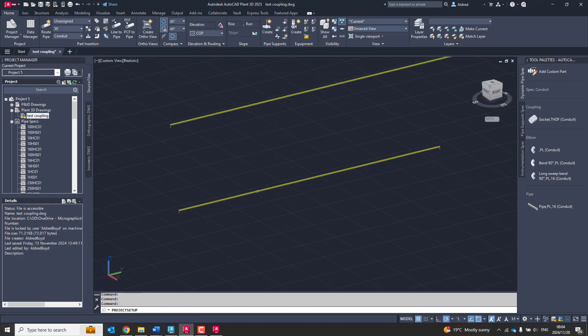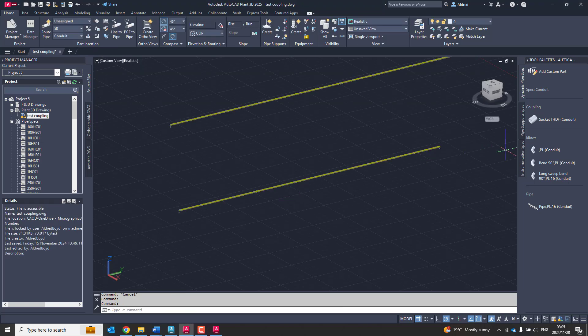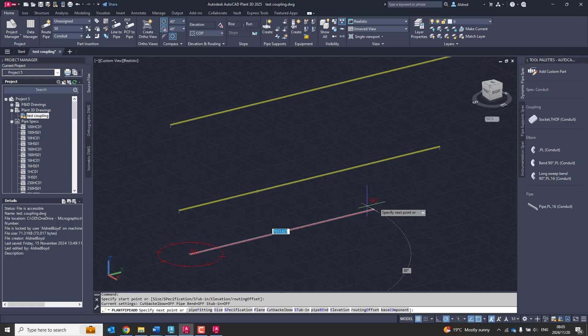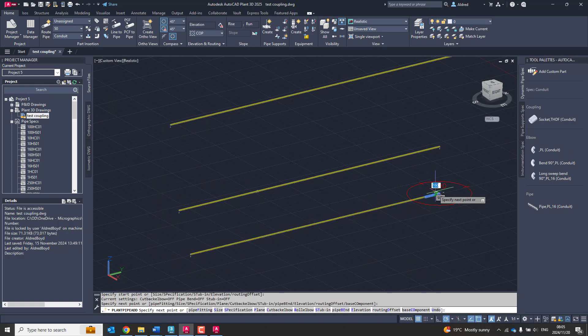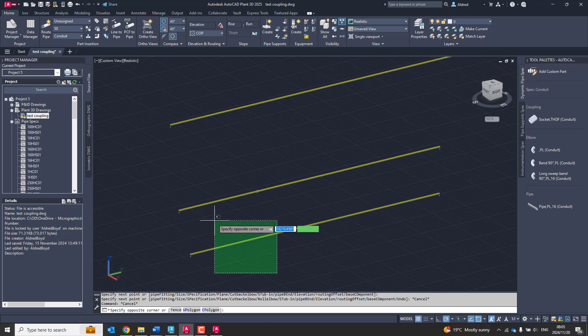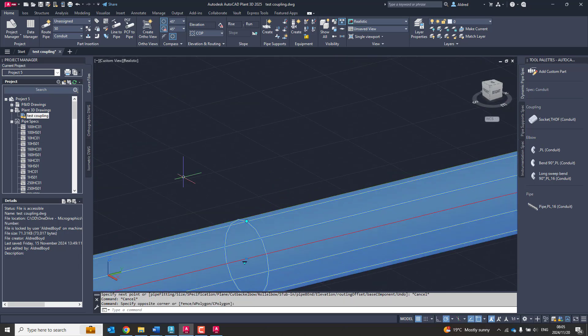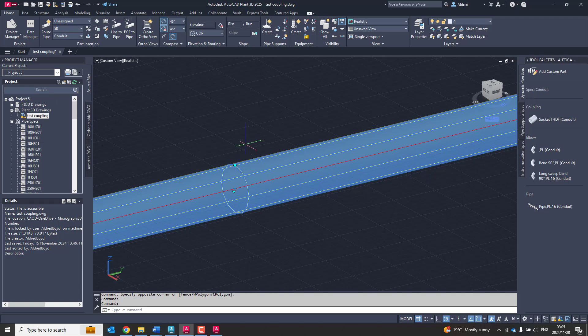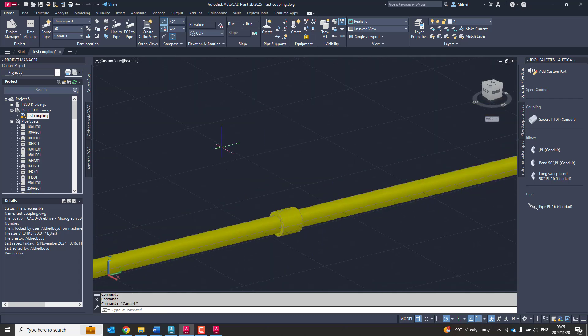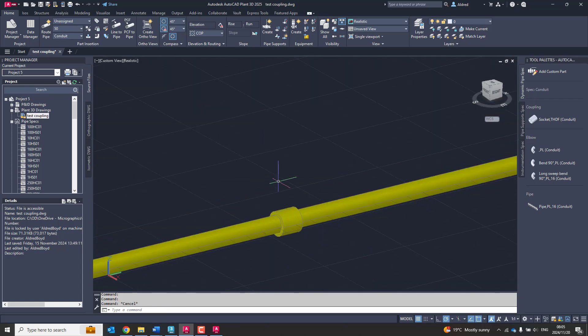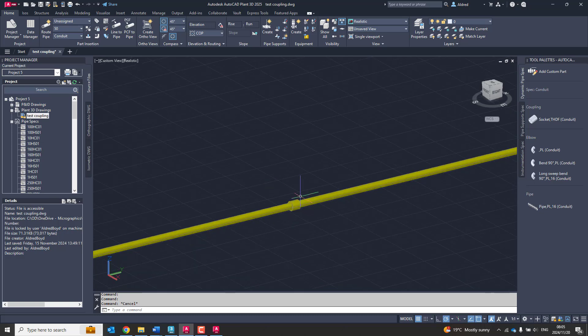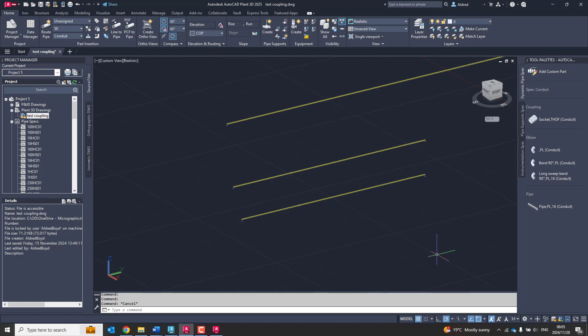Now because you've added it, so it should now add the coupling over here. So let's go and route the pipe. Let's check it. And it hasn't. But notice this over here. There is a little drop-down arrow, substitute part, and when I select that, you'll see that I've got the option to put the joint coupling in. So it is present there. It does recognize that I have created that compound joint, but it's not automatically putting it in. So what do we need to change for the automation of that coupling?